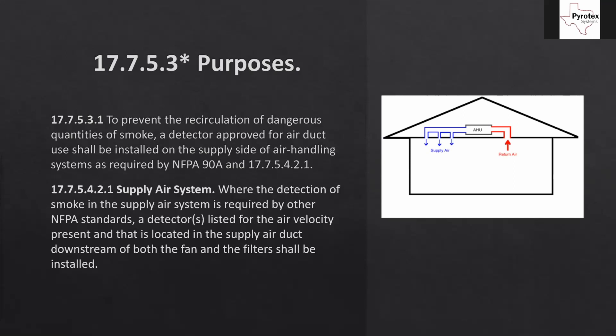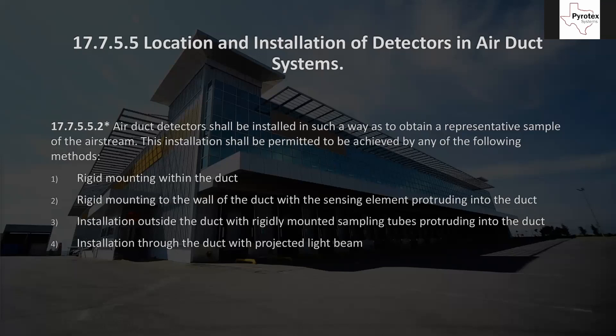So the supply air duct detector goes on the supply side, and it has to go before the duct branches off — though the 72 doesn't explicitly say that here. Now we get to the location and installation of detectors in air duct systems. Air duct detectors shall be installed to obtain a representative sample of the airstream. This can be achieved by any of the following methods: rigid mounting a smoke detector inside the duct, or rigid mounting to the wall of the duct with the sensing element protruding into the duct.